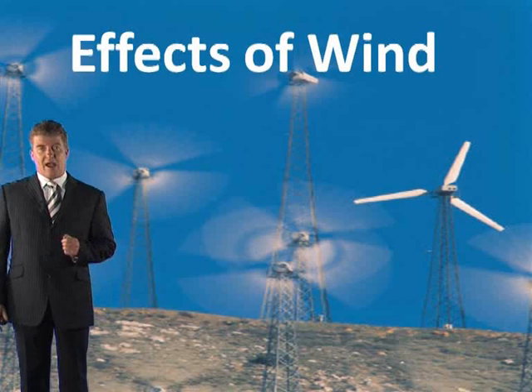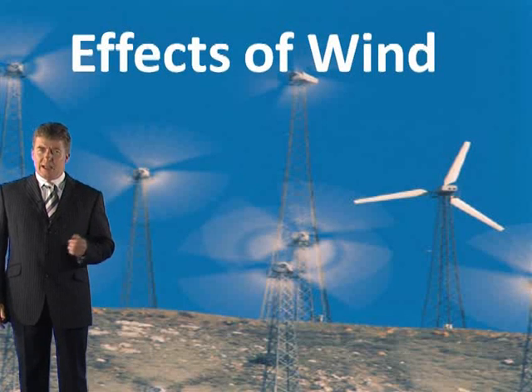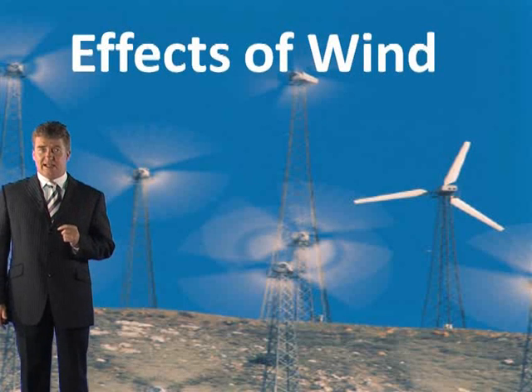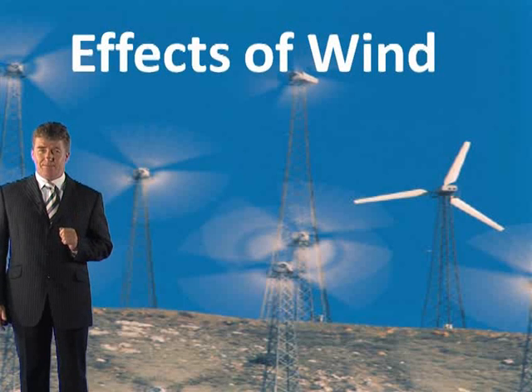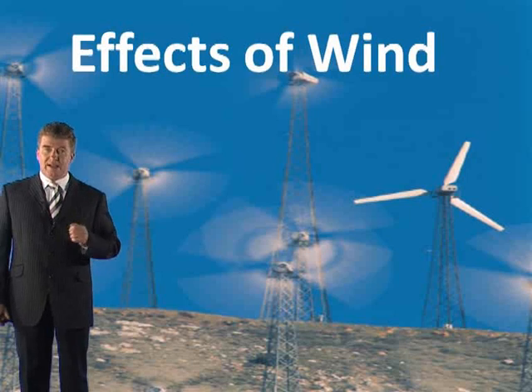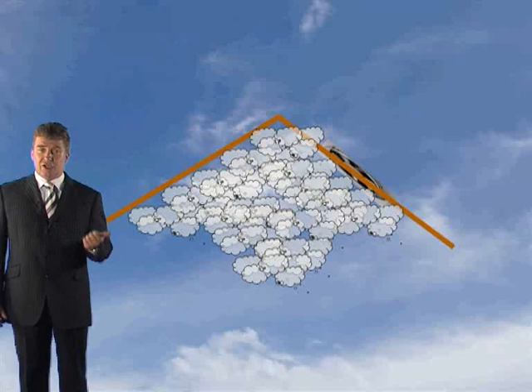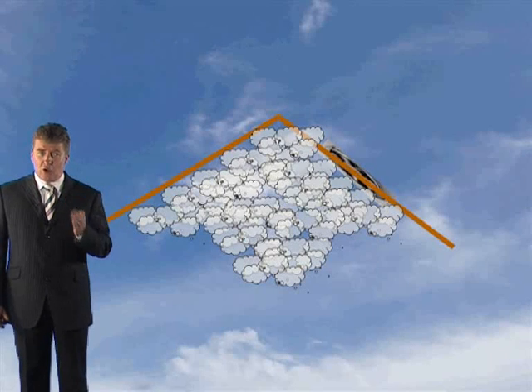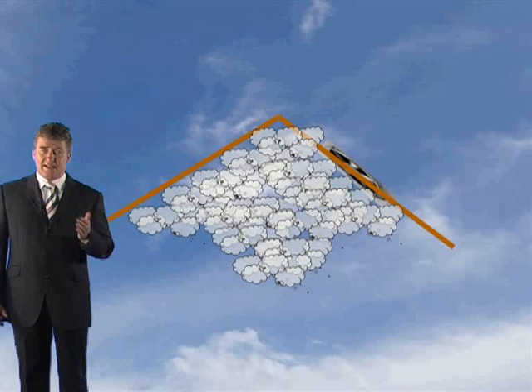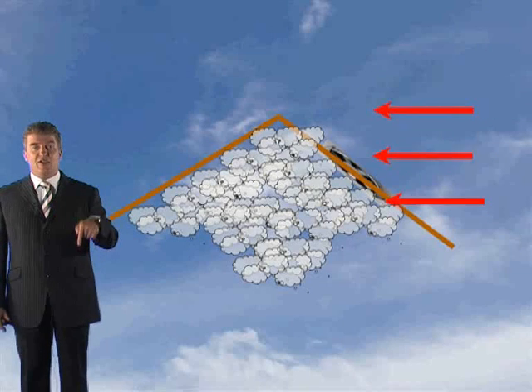The next area I'm going to consider is the effects of wind. Where natural ventilators are used for smoke extraction, it's important that they are positioned where they will not be adversely affected by external wind conditions. Positive wind pressure can be much greater than the pressures developed by a cooler smoke layer, and if this occurs at a smoke exhaust opening, the ventilator may act as an inlet rather than extract.